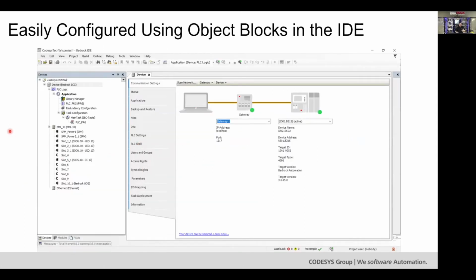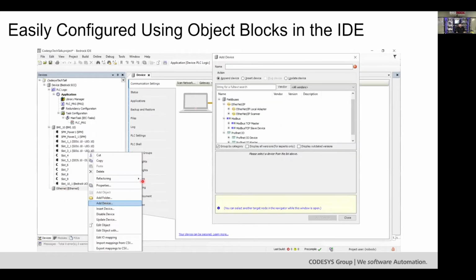For all you using CODESYS, this will have the same look and feel that you're used to. It becomes very easy to now implement the devices into your environment. You just come in, you can right click on your Ethernet adapter, add a device, and choose which protocols you want to add. You don't need to worry about special modules, just the CODESYS stack supports all the protocols that get leveraged through the hardware. So with a single module, say on a Bedrock controller, you're able to connect to whatever legacy devices you want. It really makes the whole process streamlined, efficient, and really easy to configure.